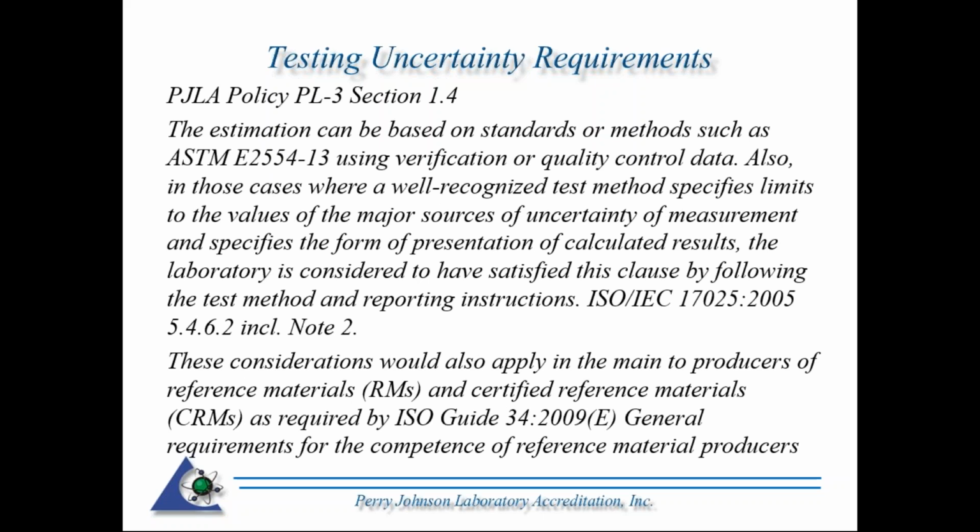The estimation can be based on standards or methods such as ASTM E2554-13, using verification or quality control data. Also, in those cases where a well-recognized test method specifies the limits to the values of the major sources of uncertainty of measurement and specifies the form of presentation of calculated results, the laboratory is considered to have satisfied this clause by following the test method and reporting instructions, which is included in ISO 17025 note number two. These considerations would also apply to the producers of reference materials and certified reference materials, as required by ISO Guide 34, general requirements for the competence of reference material producers.